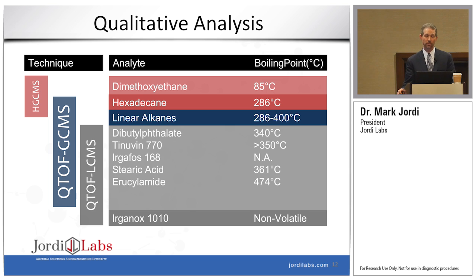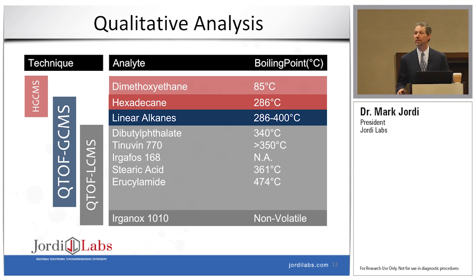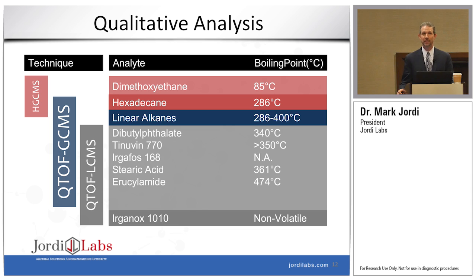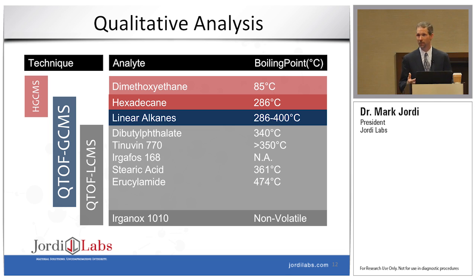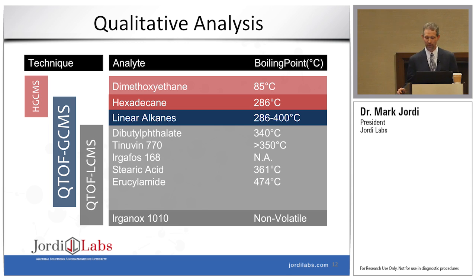In this particular figure, what I'm showing is that if I were not to run Headspace GCMS, I would be missing the most volatile components. If I didn't run QTOF GCMS, I'd be missing those semi-volatile components. And if I don't run QTOF LCMS, I'm going to miss those low-volatility components that are very polar. So it's important to run a variety of techniques that cover the full range of polarities and volatilities.